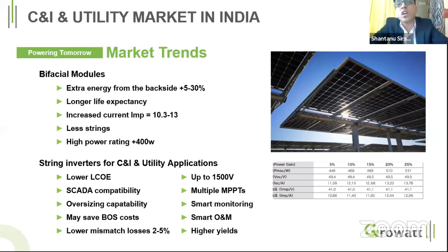Along with that, we are coming up with multiple MPPTs. When the inverter has multiple MPPTs, shadowing due to clouds or other factors will not affect the overall generation of the inverter. Due to multiple MPPTs, only the particular affected MPPT is impacted, while the rest keep running at full capacity. This is again an advantage we get with multi-MPPT inverters.